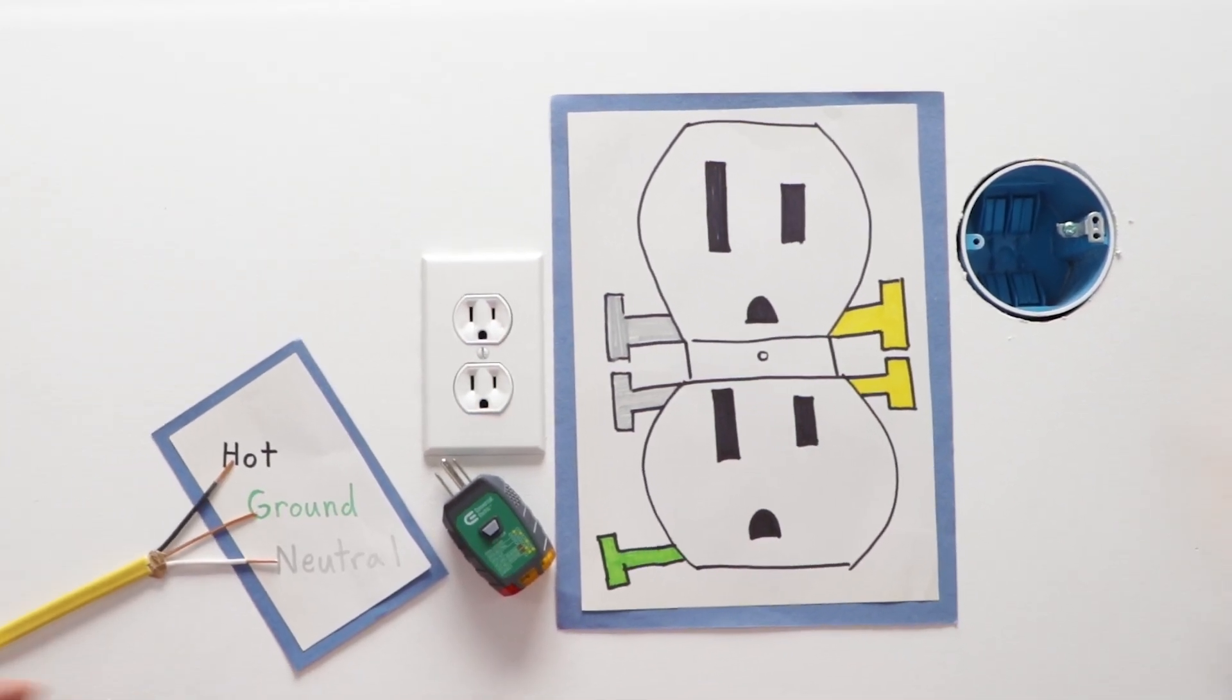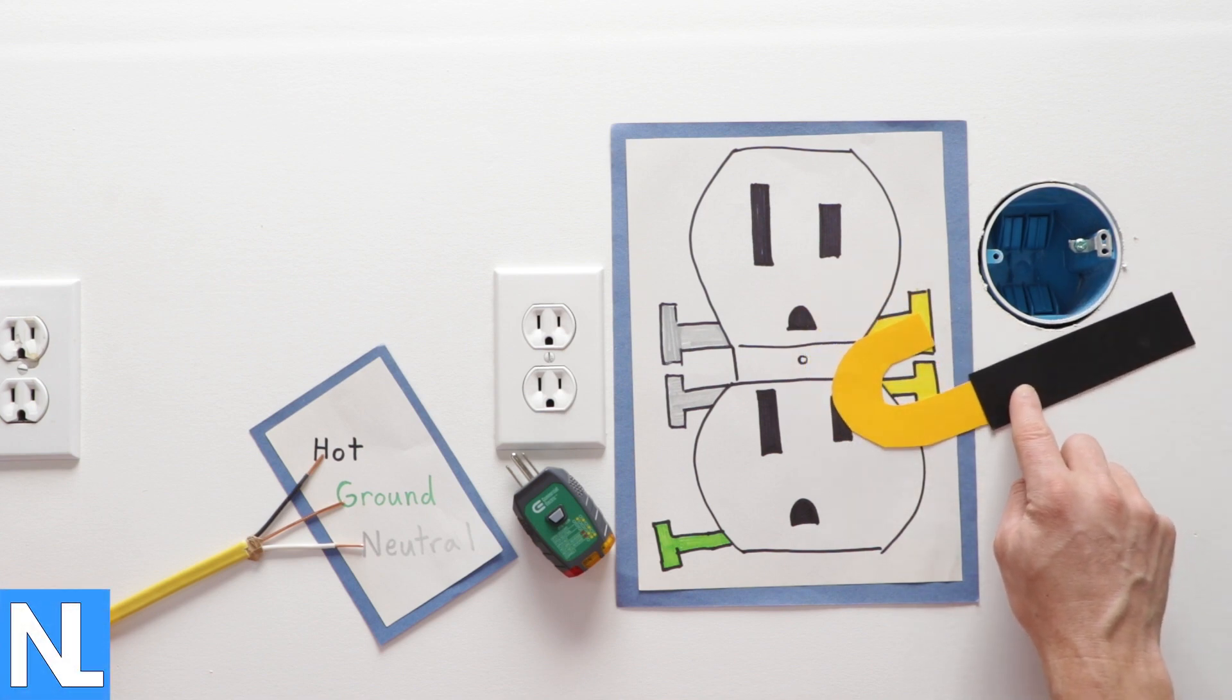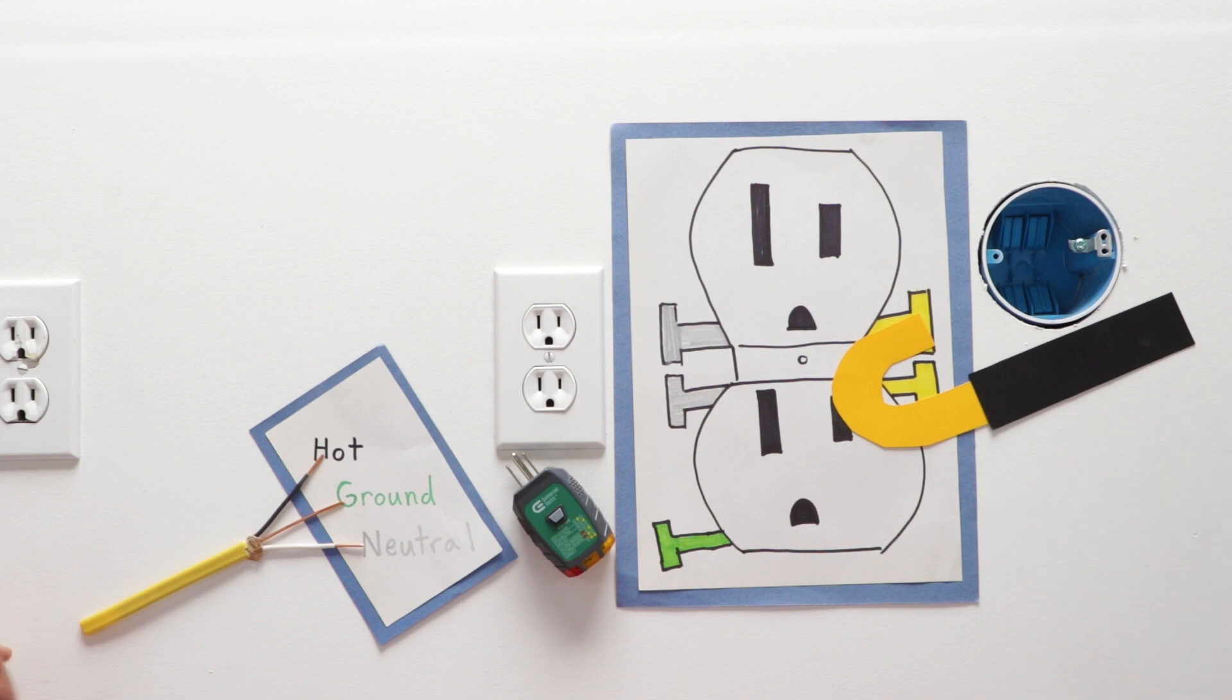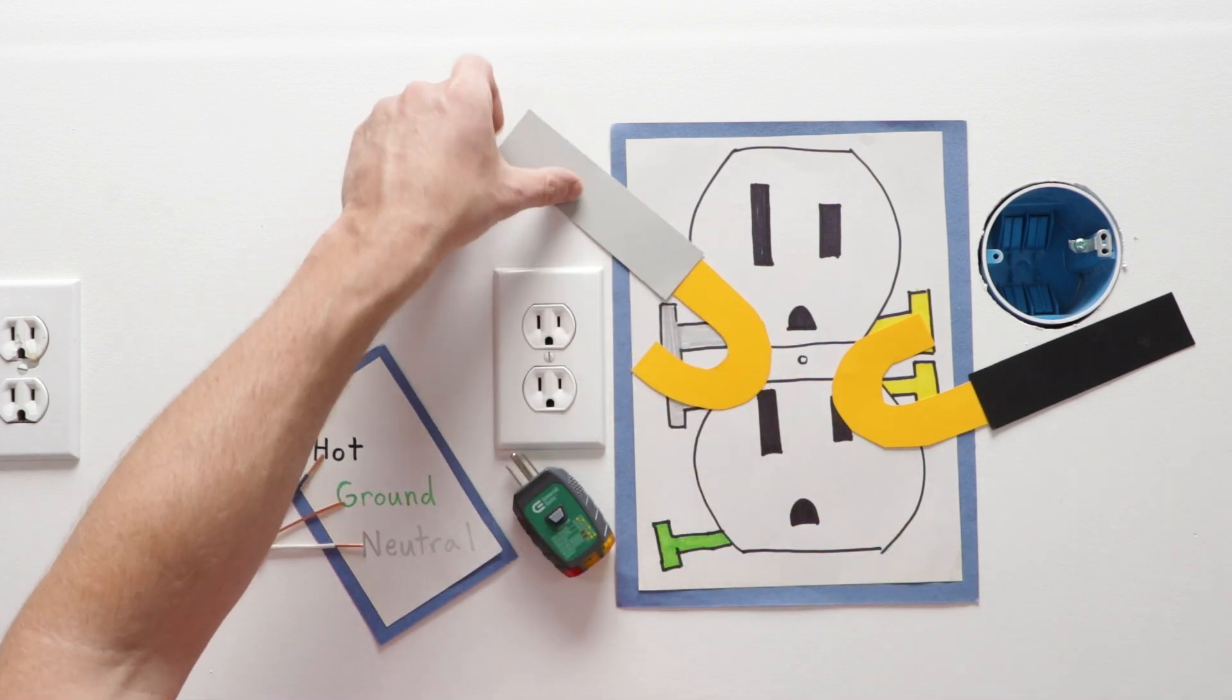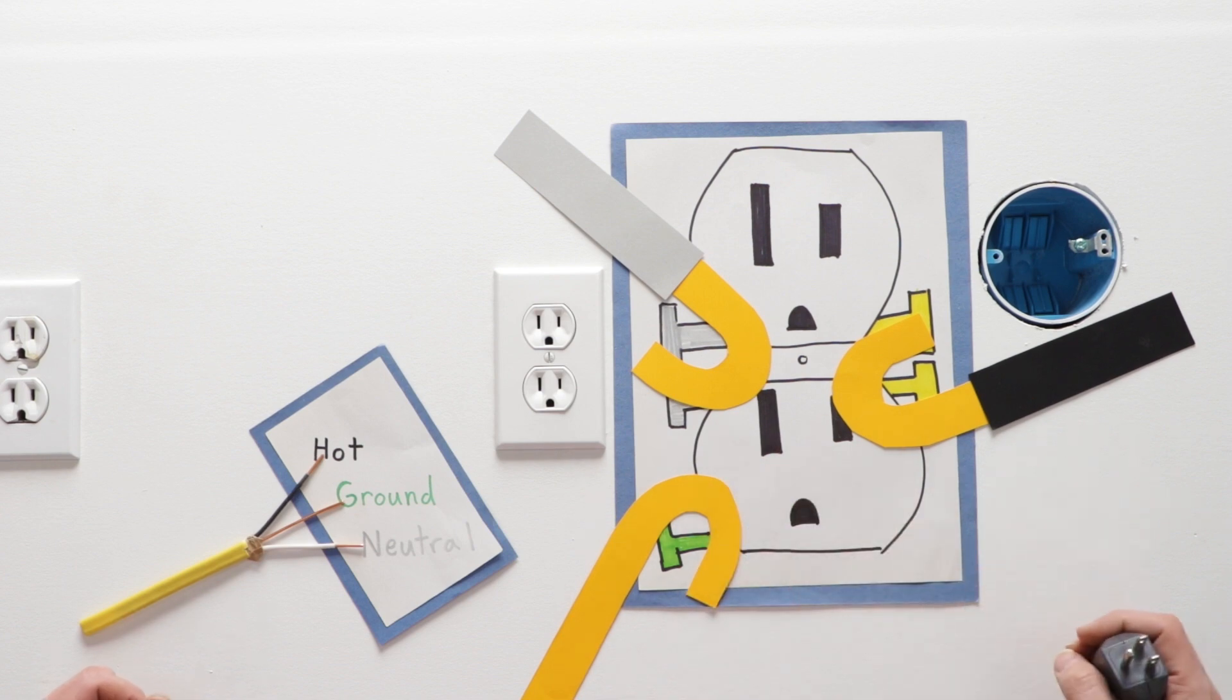As you probably know, the brass screw is for your black wire or your hot wire. The silver is for your white wire or your neutral. The green is for your bare copper or ground. This is how your receptacle should be wired.